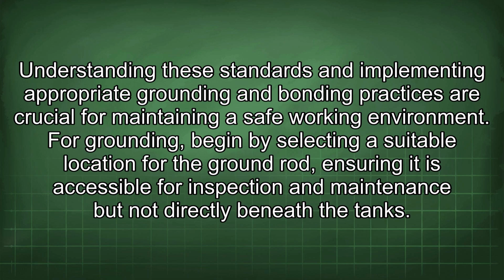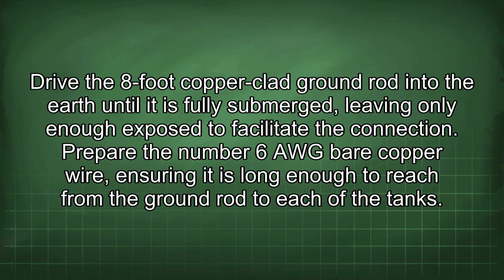For grounding, begin by selecting a suitable location for the ground rod, ensuring it is accessible for inspection and maintenance but not directly beneath the tanks. Drive the 8-foot copper-clad ground rod into the earth until it is fully submerged, leaving only enough exposed to facilitate the connection. Prepare the number 6 AWG bare copper wire, ensuring it is long enough to reach from the ground rod to each of the tanks.